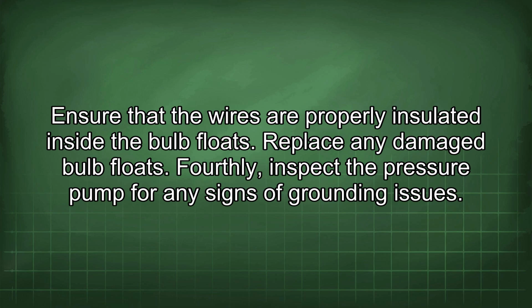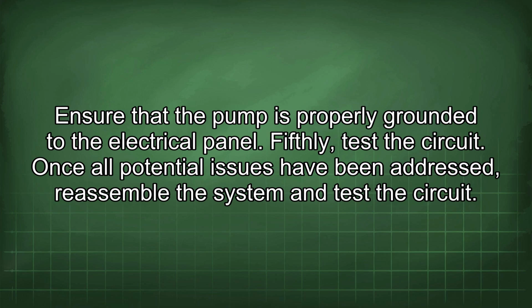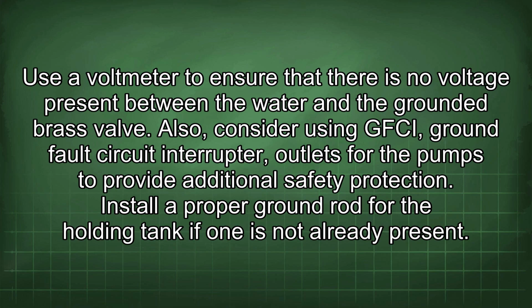Fourthly, inspect the pressure pump for any signs of grounding issues. Ensure that the pump is properly grounded to the electrical panel. Fifthly, test the circuit. Once all potential issues have been addressed, reassemble the system and test the circuit. Use a voltmeter to ensure that there is no voltage present between the water and the grounded brass valve. Also, consider using GFCI, ground fault circuit interrupter, outlets for the pumps to provide additional safety protection.